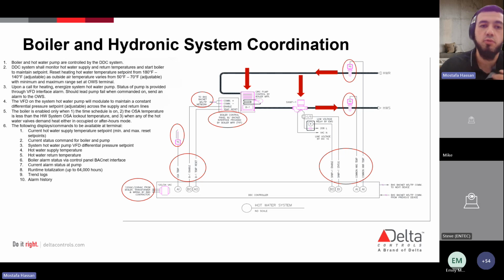Okay, I know that I'm going to run a communication point, right? Or well, depending on how it's written, it could be hardwired. It could be a communication, like a BACnet point, run straight to the panel to collect information from that boiler, right? Your DDC system shall monitor hot water supply and return temperatures, and start the boiler to maintain the set point. There is your hot water supply temperature. There's your hot water return temperature, right? Our water is flowing this way to the building, coming back to the boiler this way.